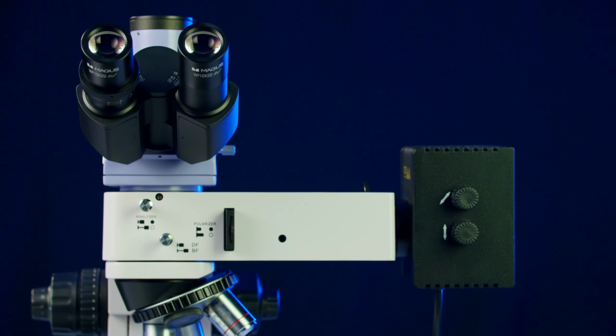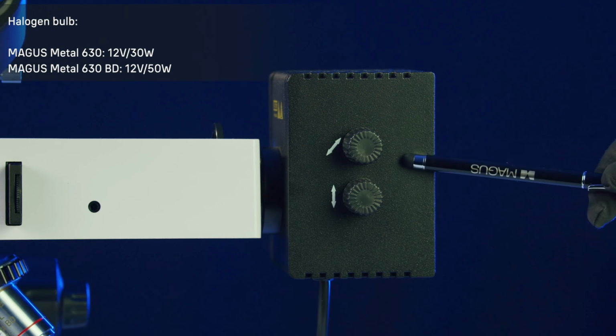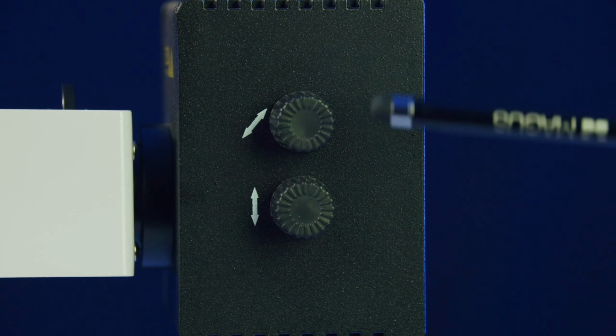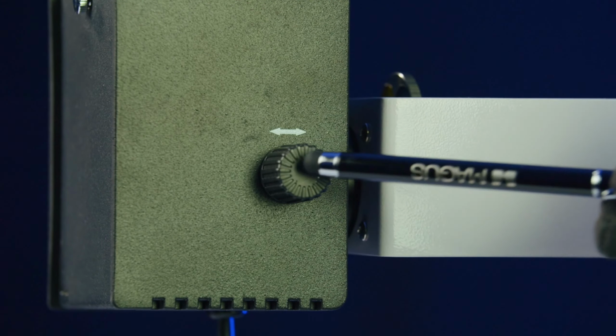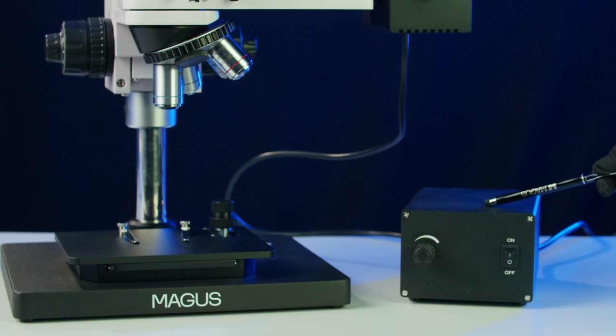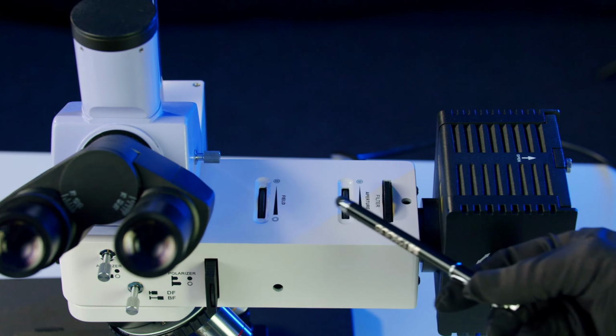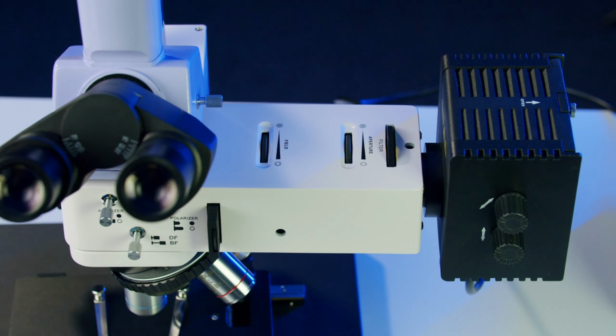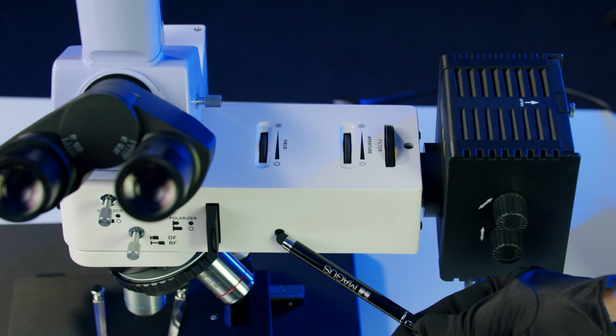Illumination system. The illuminator allows you to adjust the lighting using the Köhler method. The light source is located in the lamp housing and the lamp is centered along 3 axes. Power is supplied through a separate unit. The field and aperture diaphragms are factory centered, but if necessary, the position of the field diaphragm can be adjusted.